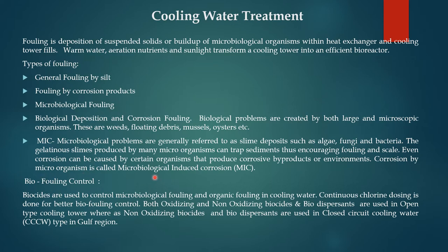Corrosion by microorganisms is called microbiological-induced corrosion (MIC). Biocides are used to control microbiological fouling and organic fouling in cooling water. Continuous chlorine dosing is done for better biofouling control. Both oxidizing and non-oxidizing biocides and biodispersants are used in open-type cooling towers, whereas only non-oxidizing biocides are used in closed-circuit cooling water (CCW) systems, where water is not exposed to sunlight and aerobic bacteria and algae growth are not present.